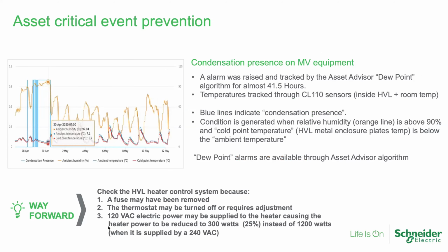Now let's go to case number two: asset critical event prevention. For this customer, we have an HVL switch with an ambient and humidity sensor inside it, and another one outside in the electrical room. Up to that point it's the same story—you want to read humidity percentage and temperature. That's something any SCADA, historian, DCS, or local software can trend and capture, setting thresholds and limits.